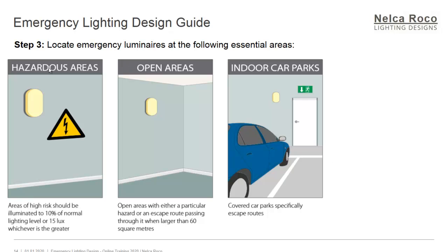Hazardous areas — areas of high risk — should be illuminated to 10 percent of the normal lighting level or 15 lux, whichever is greater. So there is a minimum of 15 lux, or at least 10 percent of the normal lighting level. If you are working in manufacturing facilities, those areas are sometimes classified as hazardous and you should meet this 10 percent or 15 lux requirement.